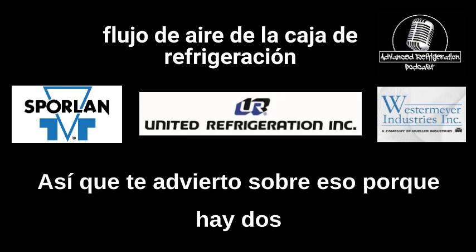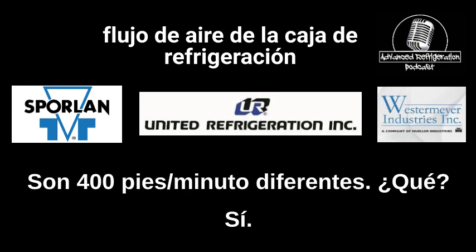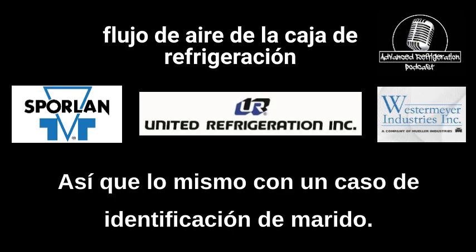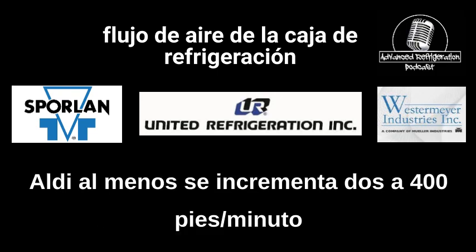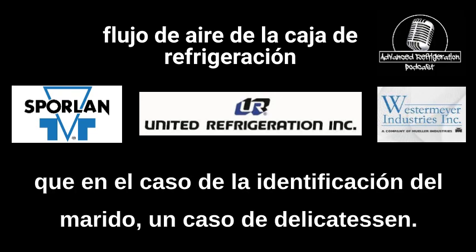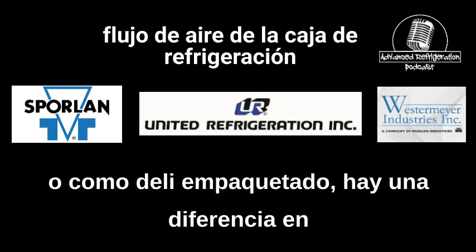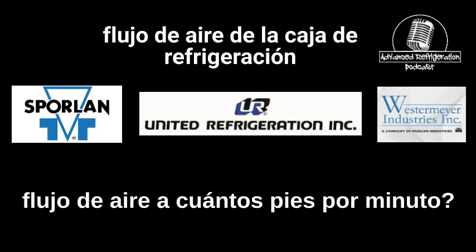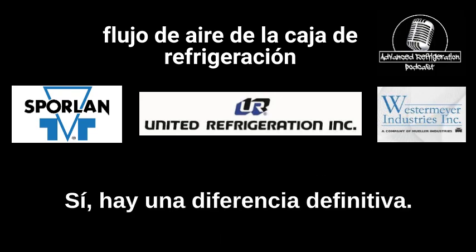So I'll caution you on that, because there are two manufacturers that do this now, that the meat cases and deli cases, they're single decks. They're 400 feet per minute different. So same thing with the Hussman ID case. The airflow on a meat ID case, at Aldi at least, is increased 200 to 400 feet per minute over the Hussman ID case, a deli case. So if it's specified for either fresh meat or packaged deli, there's a difference in airflow of how many feet per minute? I think it's anywhere from 200 to 400 feet per minute. Okay, FPMs. Yeah, there's a definite difference.